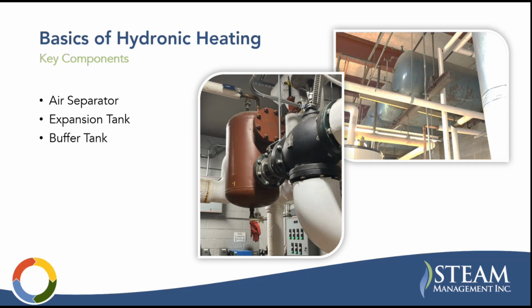I should mention too that air separators should be installed where the system is the warmest and the pressure is the lowest. So those are the locations where the gases are encouraged to come out of entrainment from the fluid, and then they can be rejected with the air vent on the air separator.